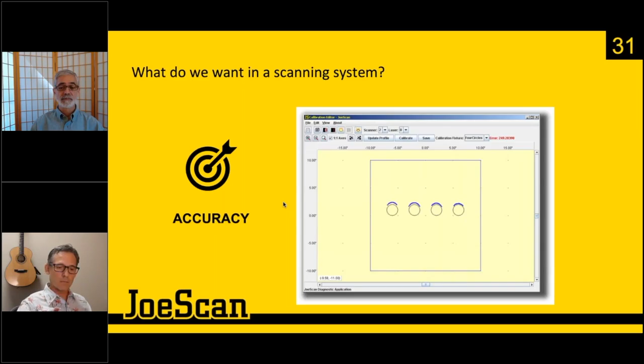You want it accurate, and one of the keys to accuracy is being able to calibrate it well. In a calibration system, the key is that it needs to be a good calibration system and get an accurate calibration. But that part's actually fairly easy. The more important thing is that it needs to be easy to do with as few steps and as little complication as possible. Because if it's difficult or complicated, there's a good chance it won't happen as often as it should. There's a good chance that when it does happen, occasionally mistakes will be made. And so we really focused on making our calibration system very, very simple and approachable, so that it's easy and quick to get a good calibration as regularly as you need.